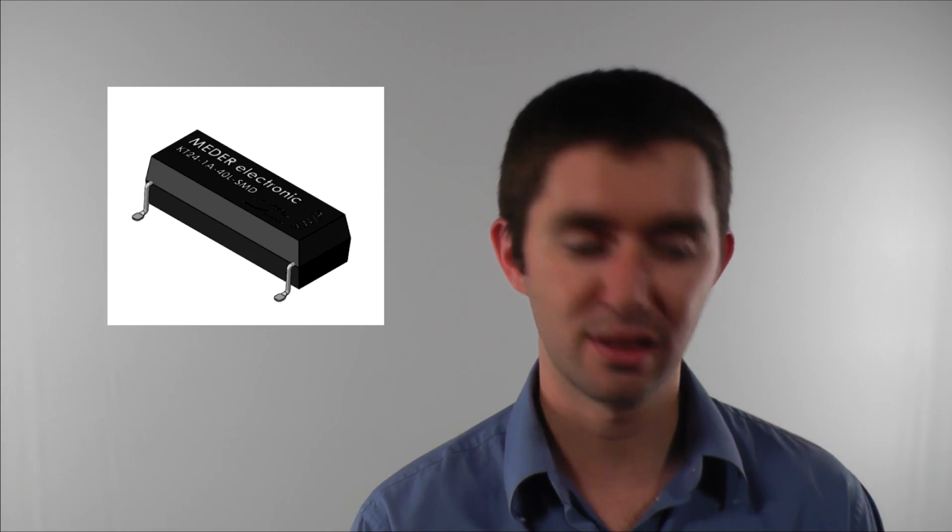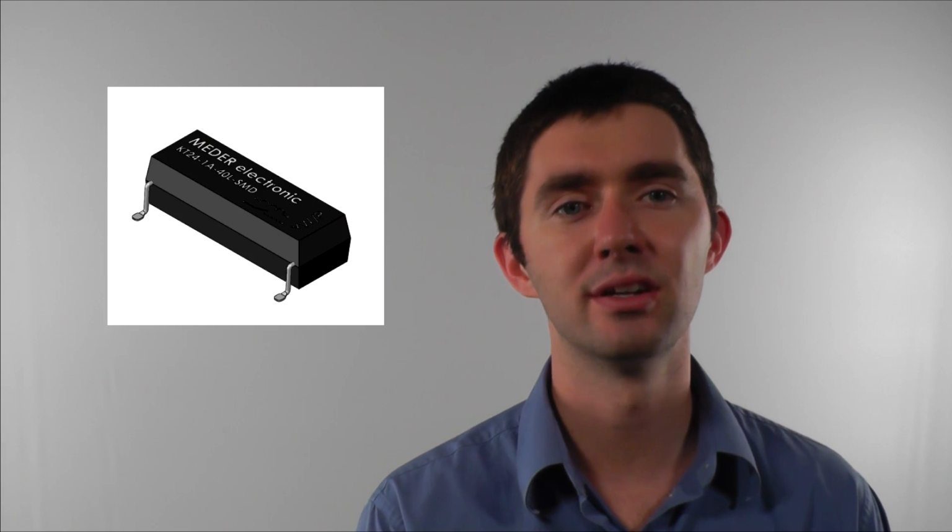And the other nice thing is when it's off, this is a new product line. This is the KT product line. They actually had a previous product line. And the KT product line can now go from, it used to be 4 kilovolts, now it's up to 8 kilovolts. So when it's off, it's really off. You can really stand off quite a lot. Not just the 1,000 volts, but also this is like insulation resistance and so on. So that's the improvement.